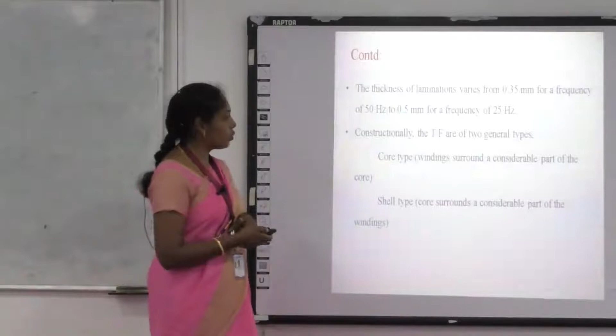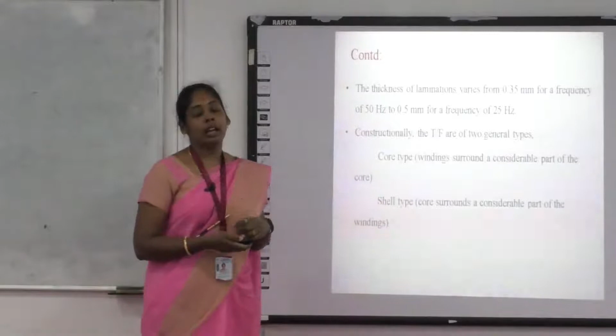The thickness of the laminations varies from 0.35 mm for a frequency of 50 Hz to 0.5 mm for a frequency of 25 Hz. So laminating the core is a major part in a transformer. If you laminate it properly, then we can reduce the eddy current losses as much as possible.